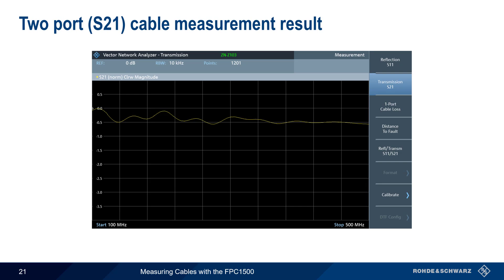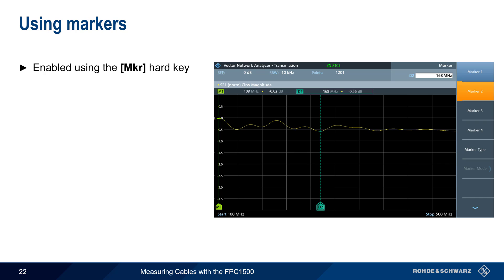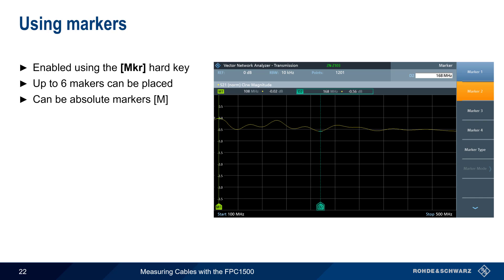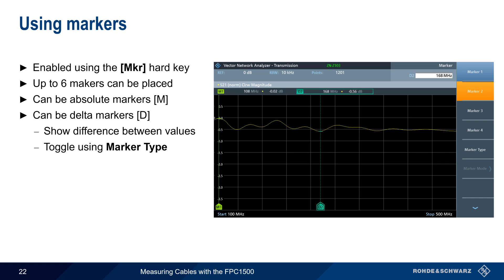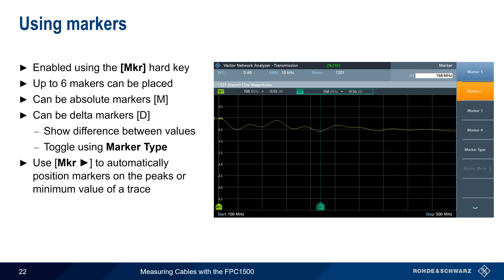Now let's look at a typical two-port or S21 cable measurement. Here again we see a plot of loss as a function of frequency. In order to analyze this in more detail, we can use markers and marker functions. Markers are enabled using the Marker hard key and can be used to examine the frequency-specific characteristics of a cable. Up to six markers can be placed on a trace, and these can be either absolute markers or delta markers, which show the difference between marker values. You can toggle between types using Marker Type. Another Marker hard key is used to automatically place markers on the peak or minimum values of the displayed trace.